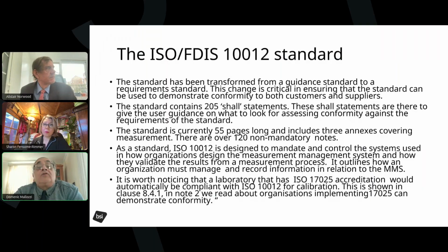There is one exception, which Alice is going to mention in a minute, so I'll mention it. If you use a calibration lab that also repairs your equipment, they have to take into account 10,012 in the repair process, not the calibration process. So the documentation needed for repair, the methodologies needed for repair have to comply with 10,012 when they're doing a repair, because 17025 doesn't discuss repairing equipment. It only discusses the calibration and test functions. Come on, the next slide, please.